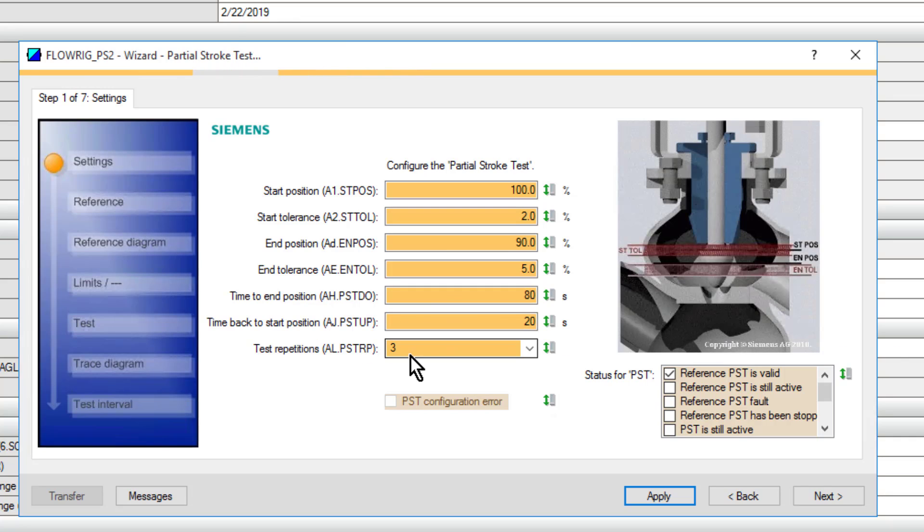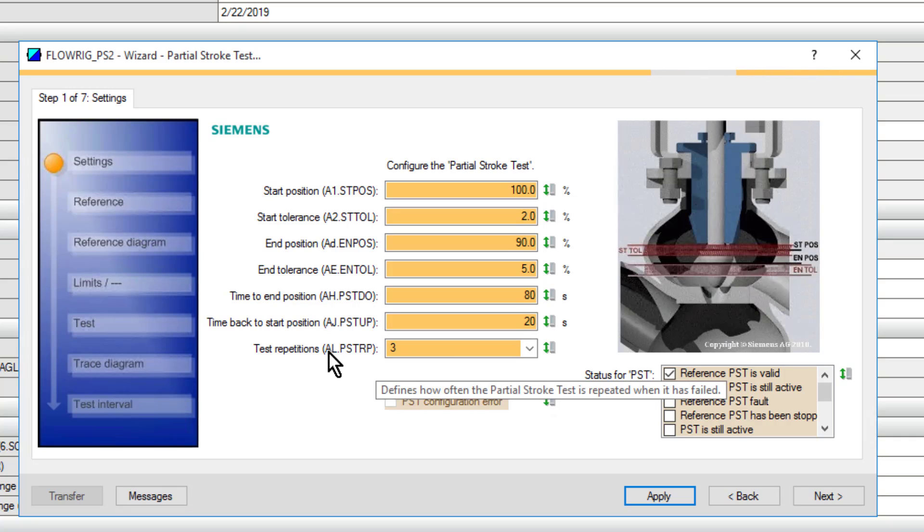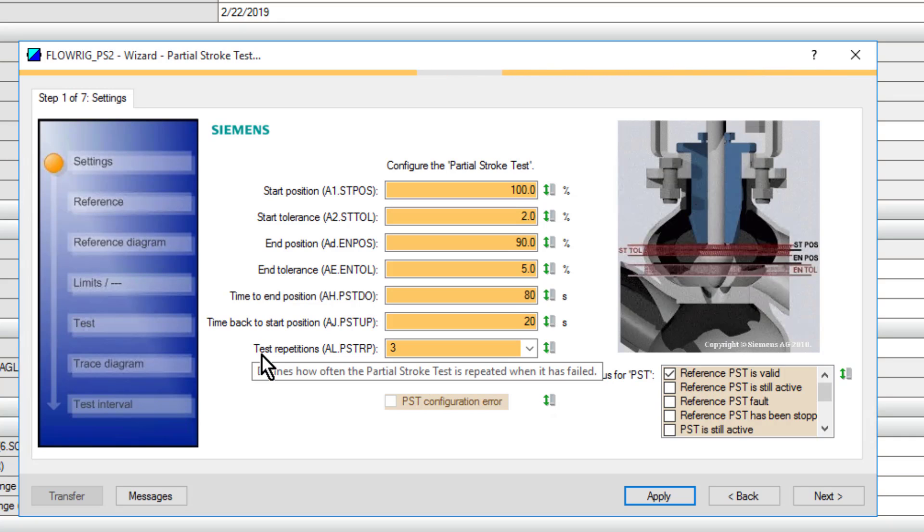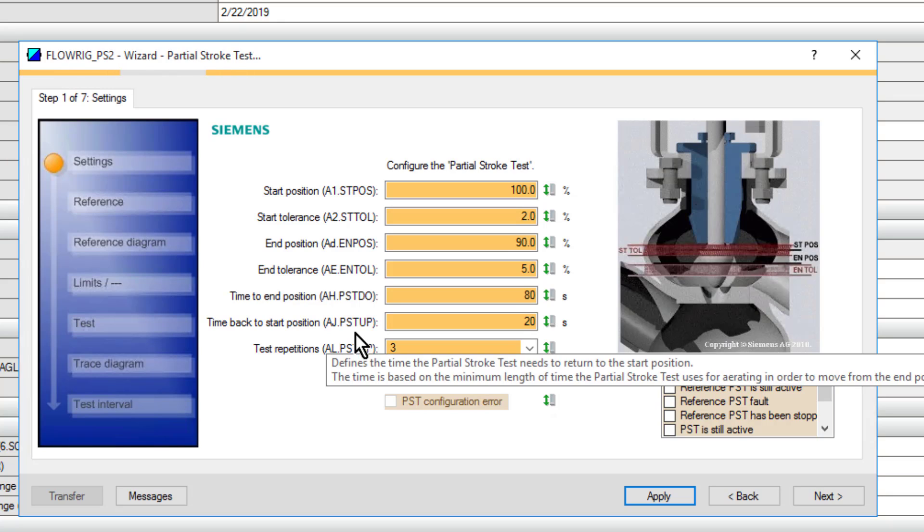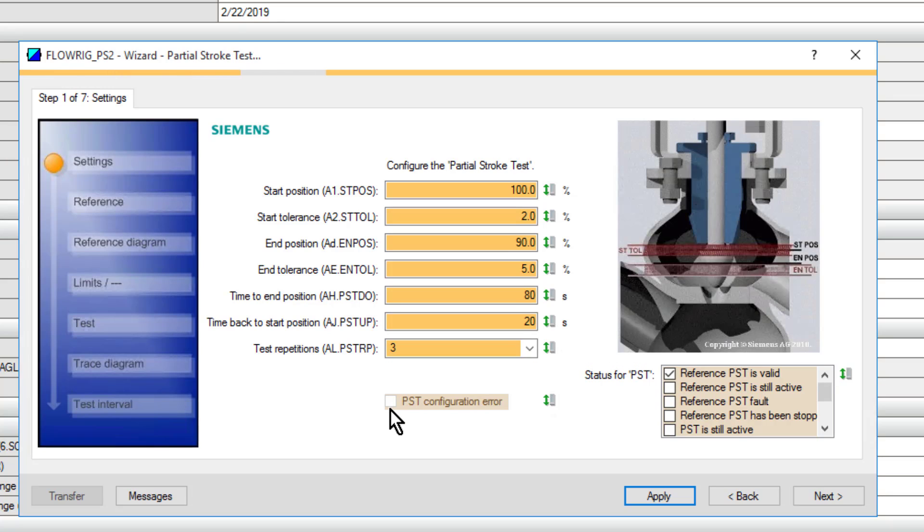A new feature for this PS2 is the amount of test cycles. If you do a partial stroke test once every three months, the likelihood is that the valve is going to stick on that first stroke test, so you get a fail. It's a simple addition - it's the number of cycles that you have to fail at. We've put 3 here, so it will do 3 cycles. If it only fails at 1, then we'll be okay. It needs to fail all 3 to give us a fault.